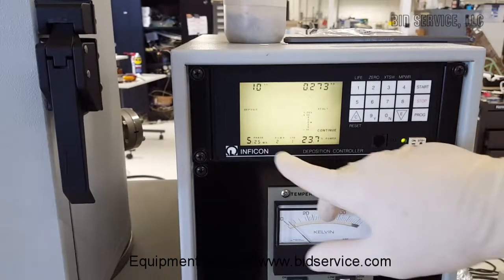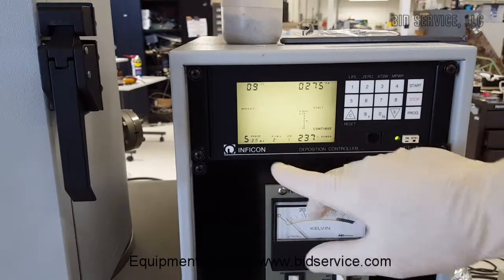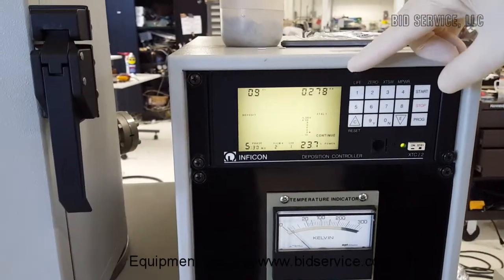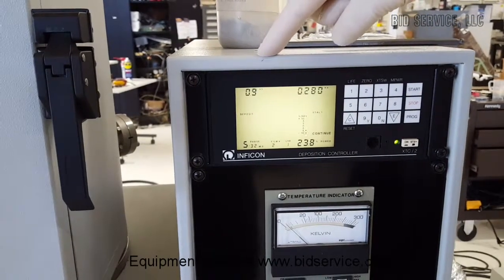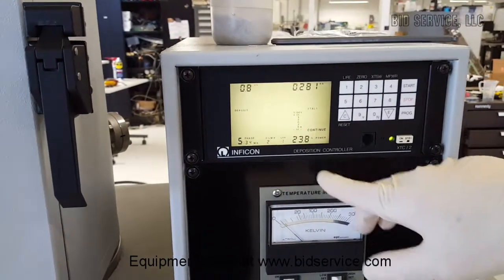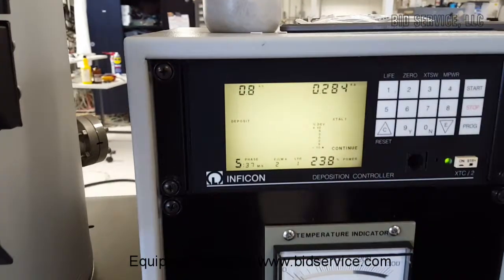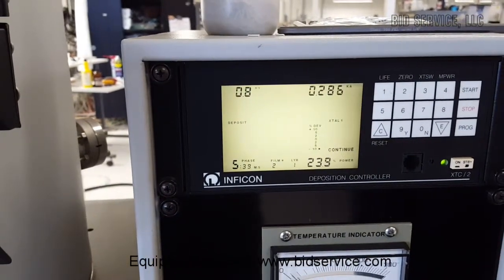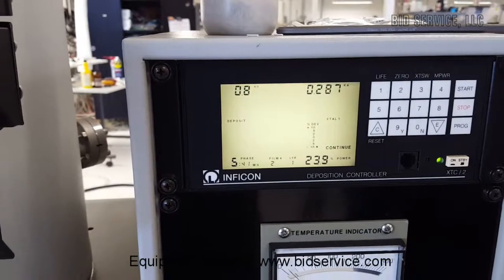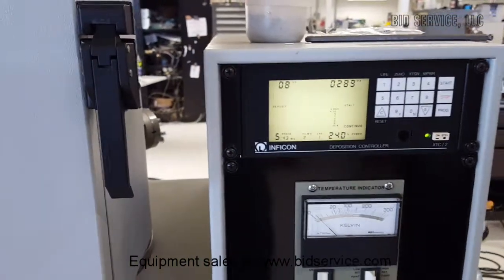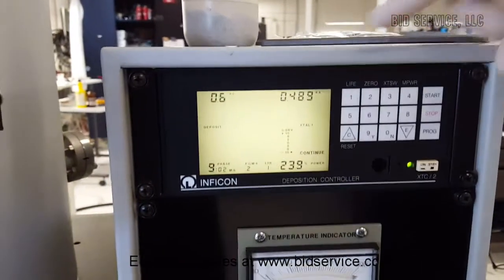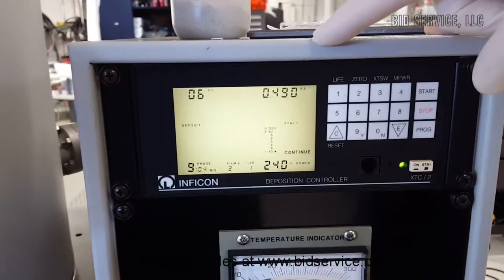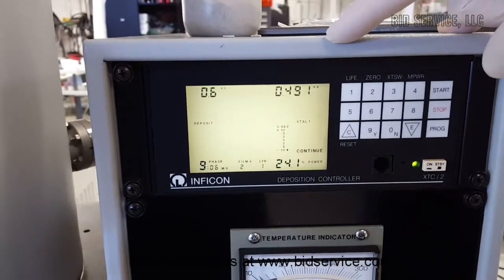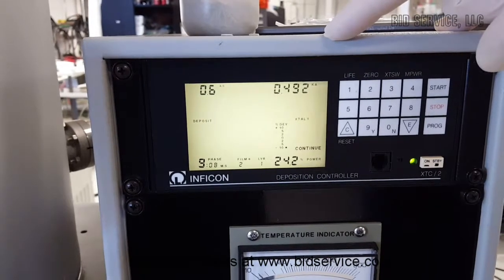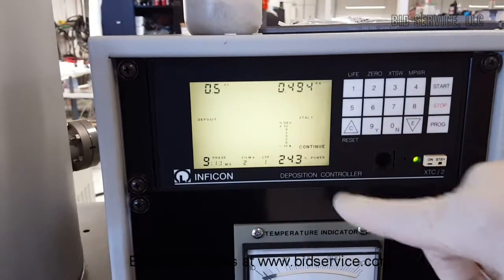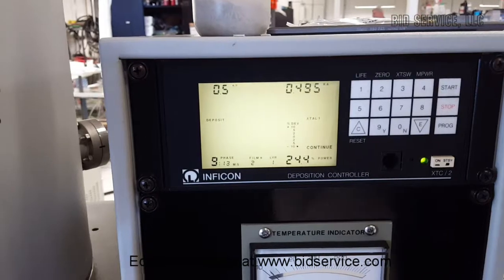Okay, so this process has been running for at least 5 minutes now. And I just want to show you that we're at 277 and we're still controlling at around 1 angstrom per second. And as I said, the power is around 23.8. So we'll come back when it's getting closer to 500 before we shut off. Okay, so we're getting near the end here. We're almost at 500. And what we're looking for here is we're going to see that the power shuts off to 0 and that the shutter is going to close and then it's going to stop.